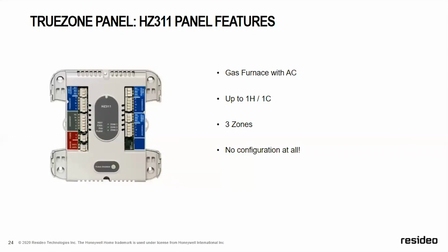If you're dealing with a Unico system, you cannot use this panel because 40 degrees is just not low enough. Believe me, I learned that the hard way on an installation in an attic, very hot, trying to figure it out. So 40 degrees is the low with the HZ311.